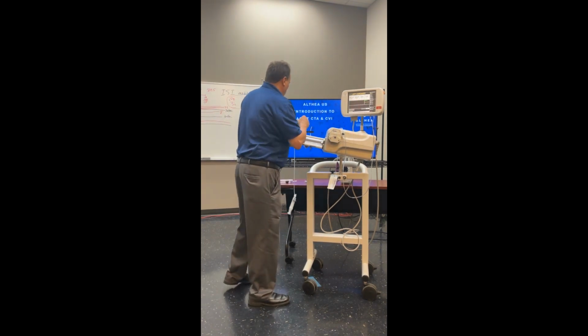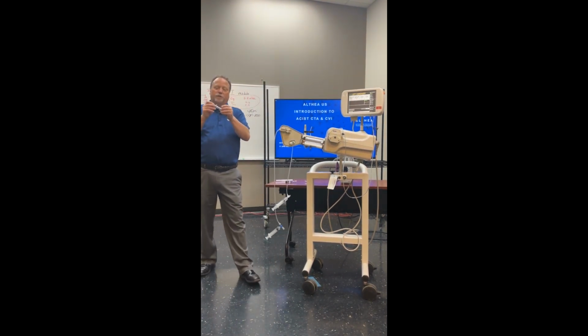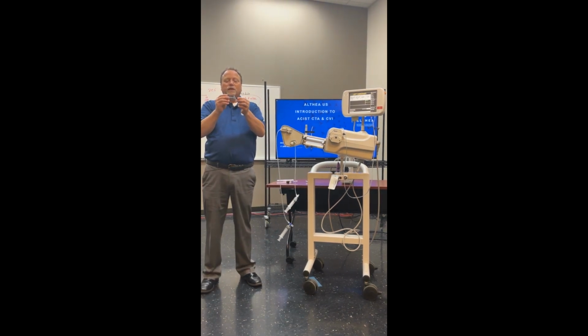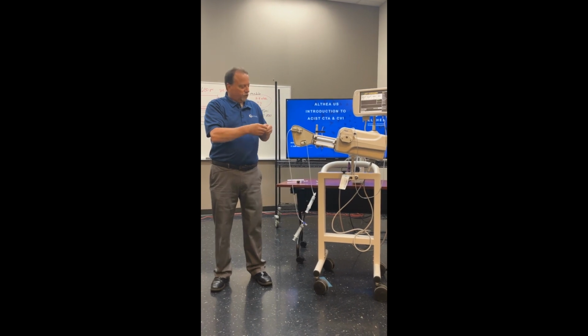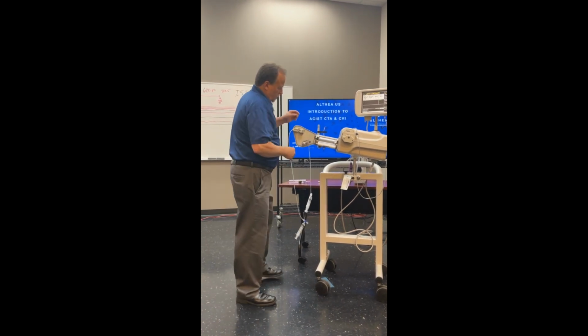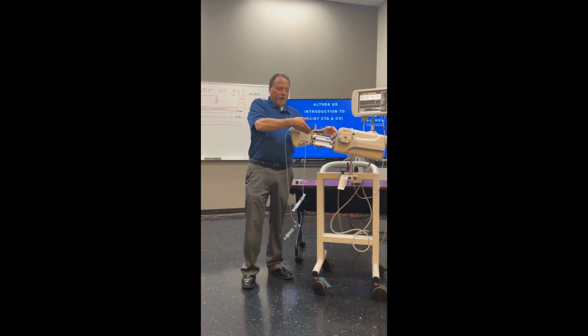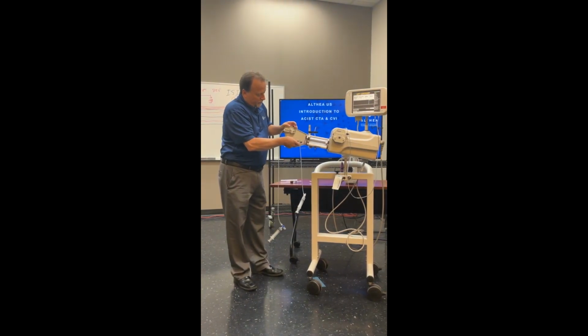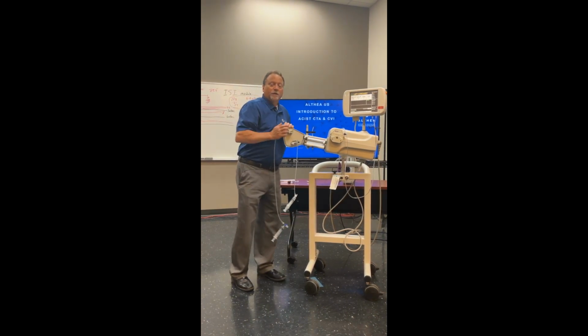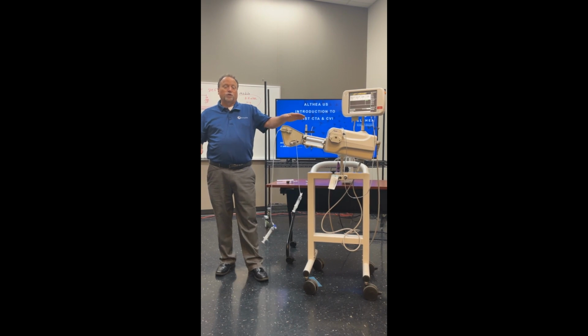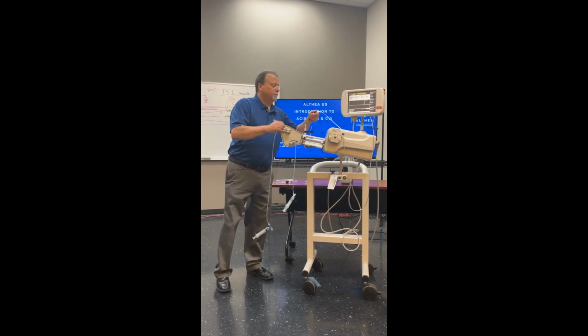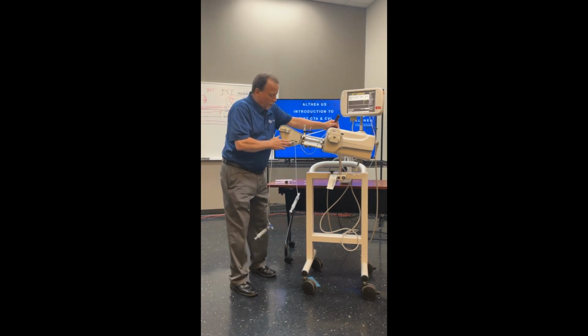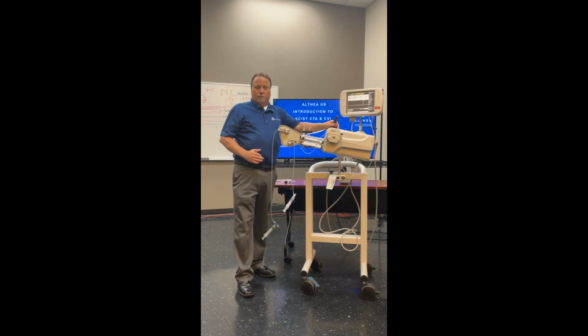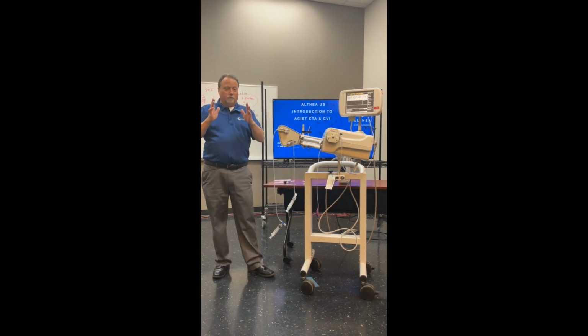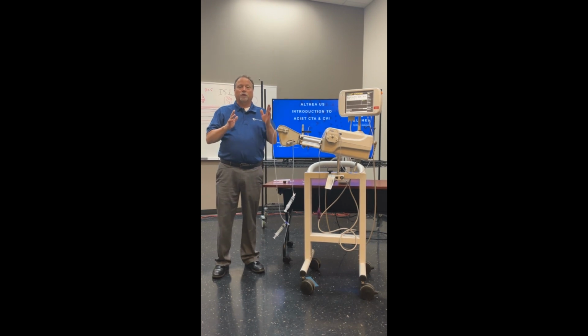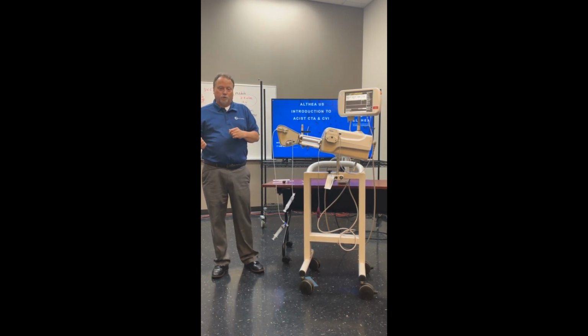We also have a manifold valve open. This is the manifold. Again, it's a test jig. And the way this operates is you'll have saline and contrast going through this. As the contrast is pushed to the patient, it will push the plunger back, cutting off the saline tubing, sending contrast to the patient. Once you're done with the contrast and you hit your saline button, it will then push the plunger the opposite way and send saline to the patient. So it is a manifold. It determines, through which button you're pushing, whether it be contrast or saline going to the patient.